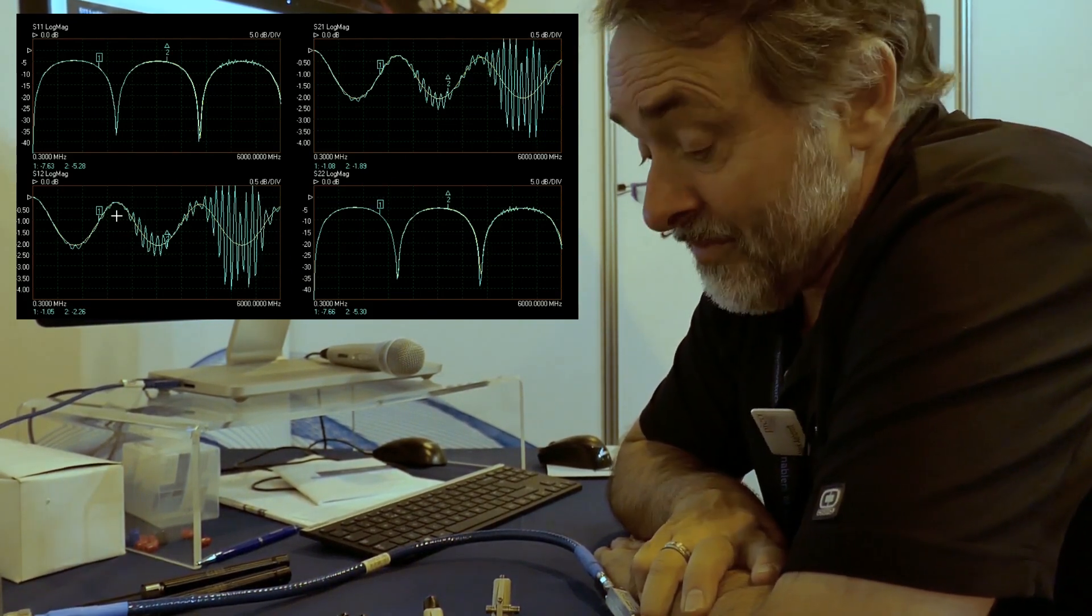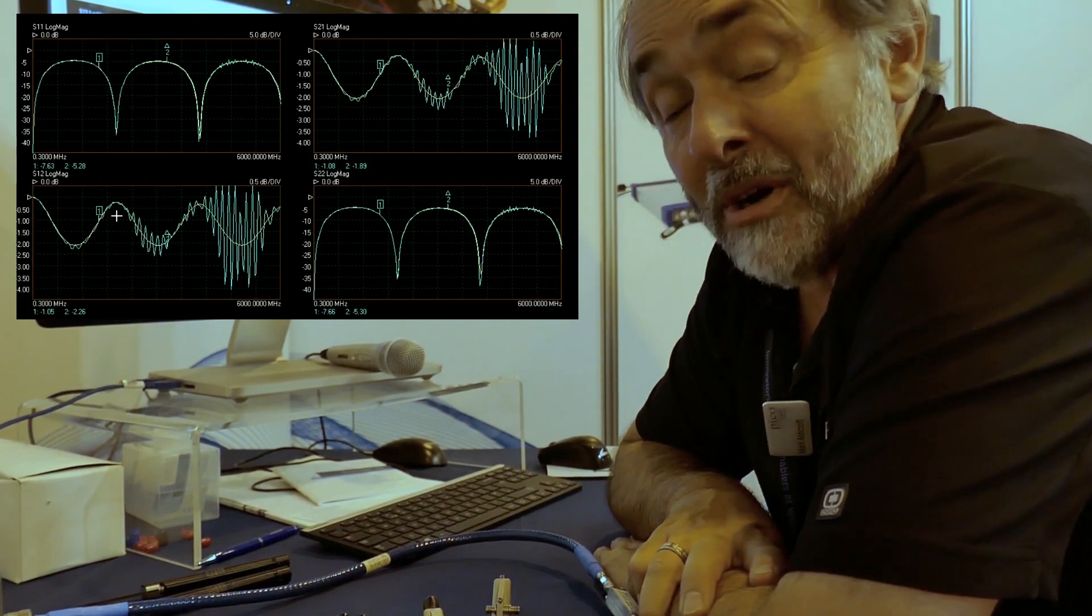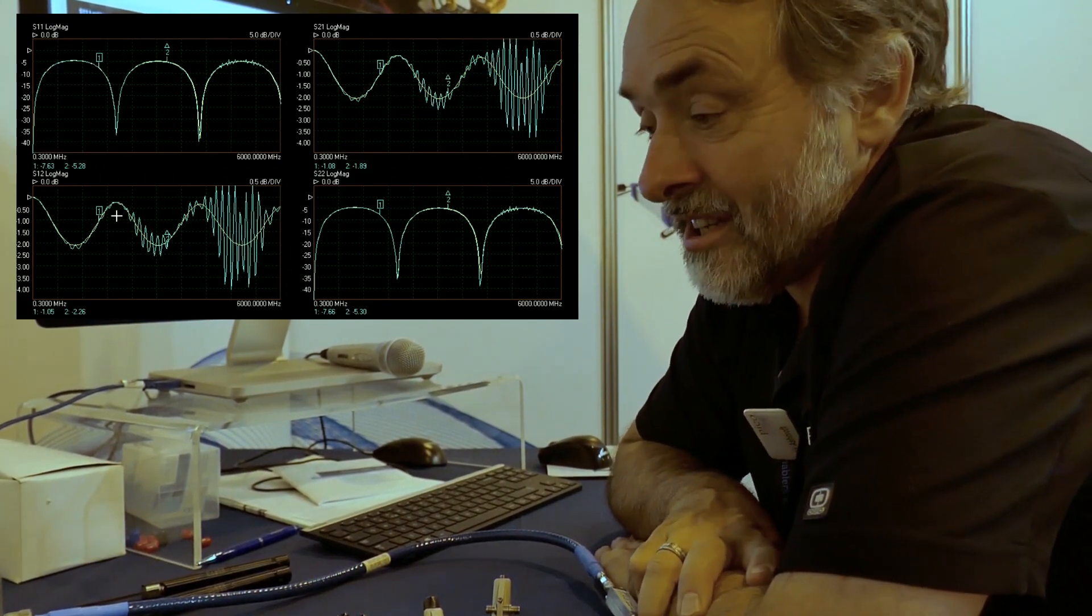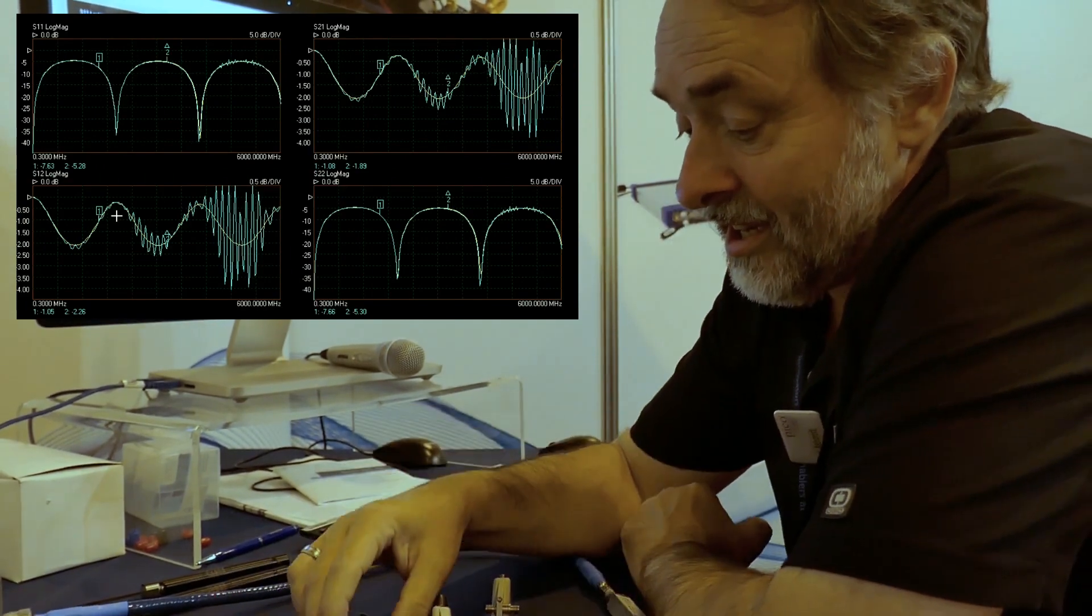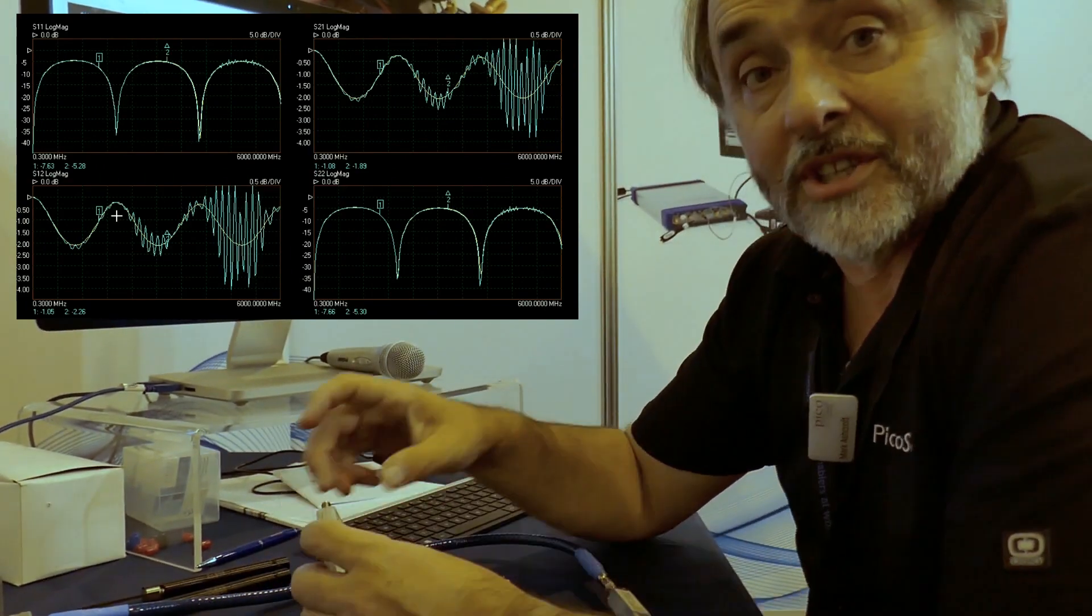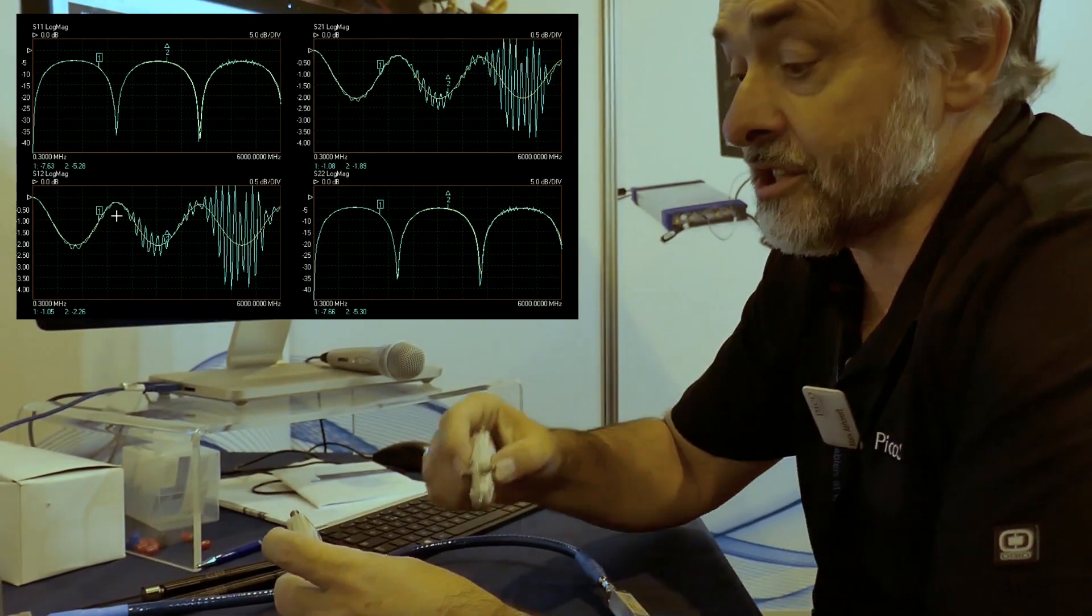Well, eventually we found that both of us had brought CAL kits for the VNA. And what we had managed to do is calibrate with one standard using the data for another standard.